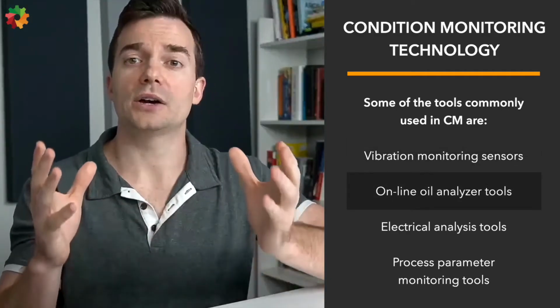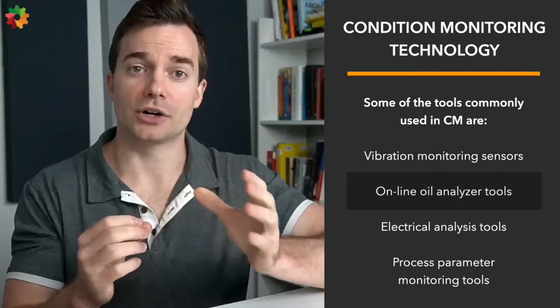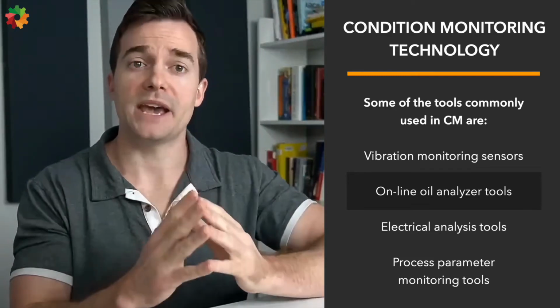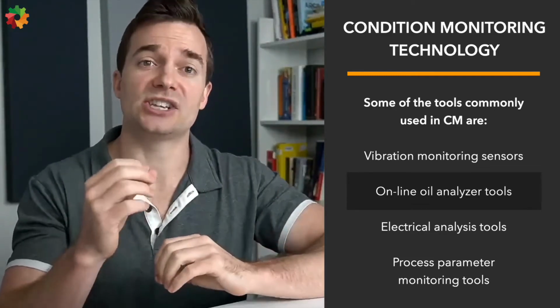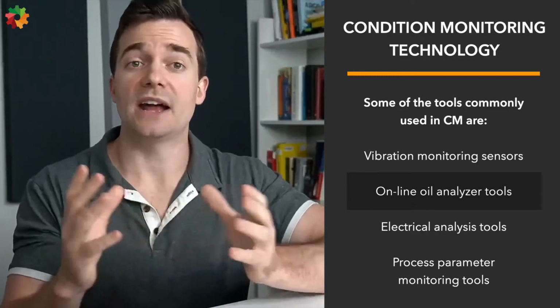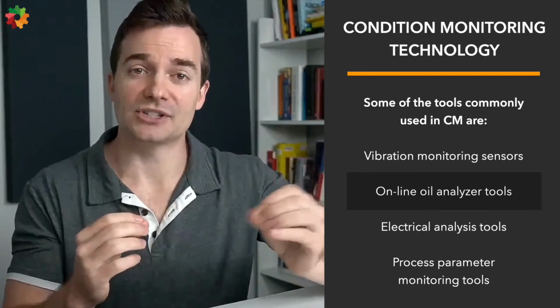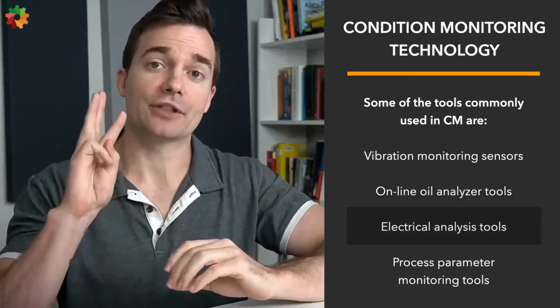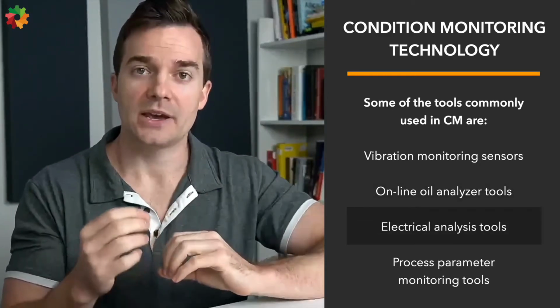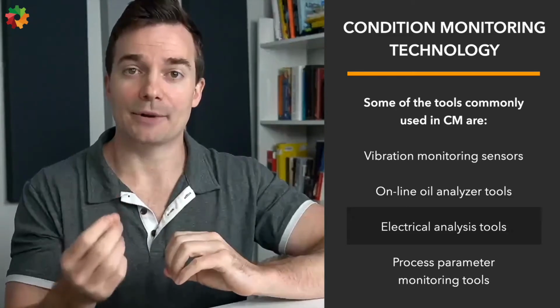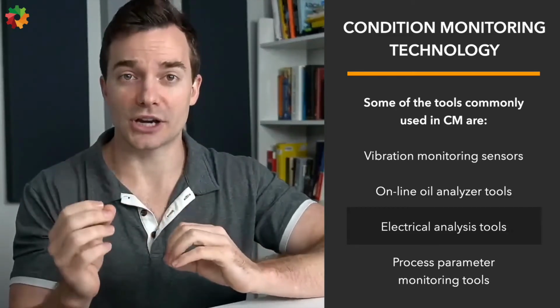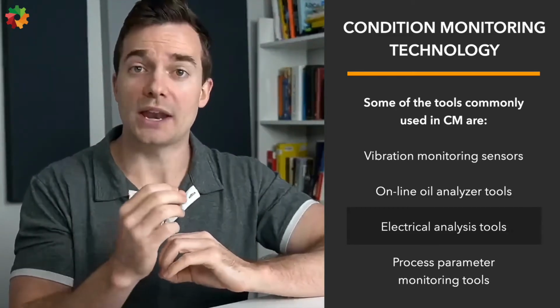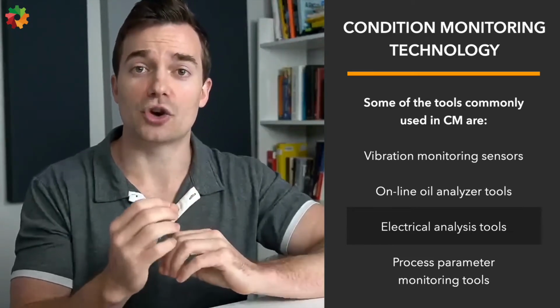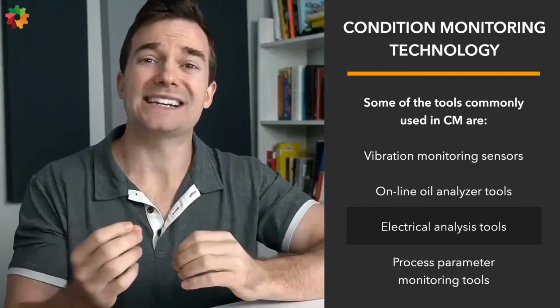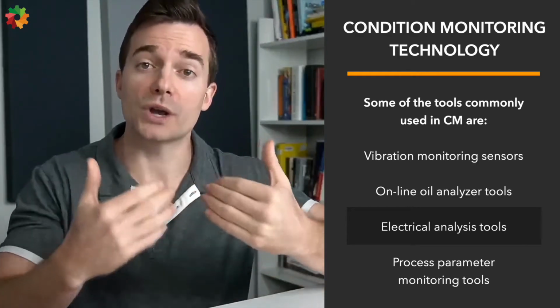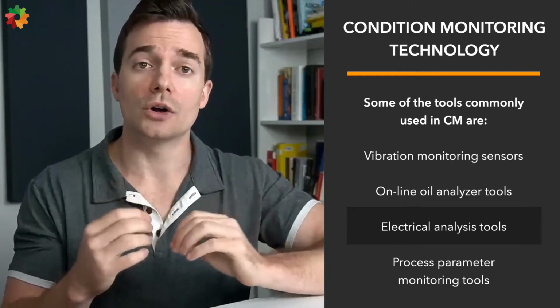And two, online oil analyzer tools, which can measure and monitor viscosity, temperature, pH, and moisture to detect when a changeout is required, or worse, if any of the oil-wetted rotating elements are approaching wear out. And then we have three, electrical analysis tool. It uses clamp-on or inline ammeters to measure current in a circuit. It helps maintenance teams gauge when equipment, such as an electrical motor, is drawing an abnormal amount of running current, which is often an indication that it may be time for motor rewind, insulation checks, or load re-verification.